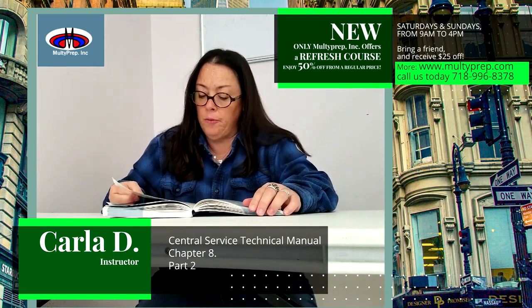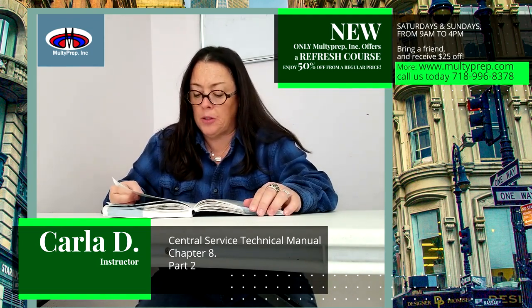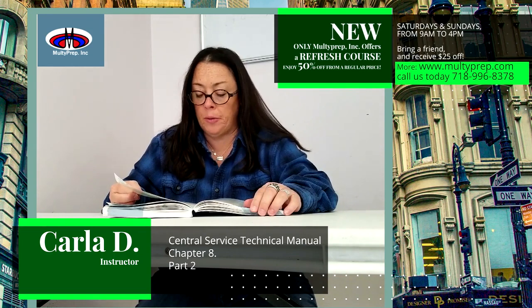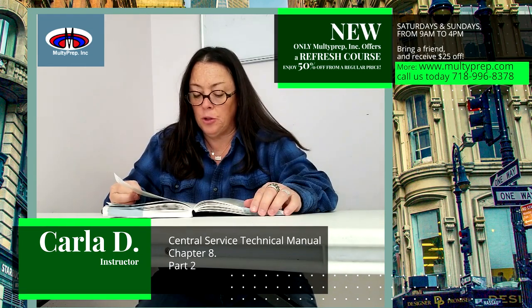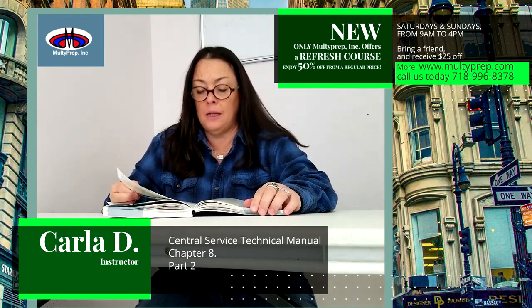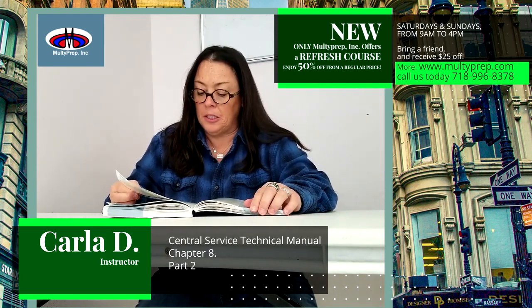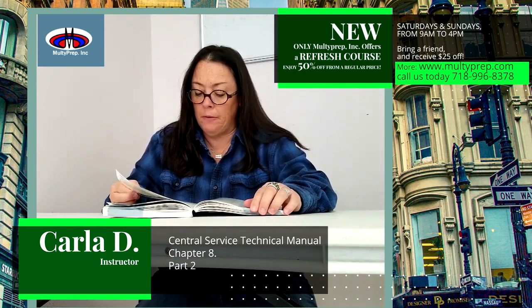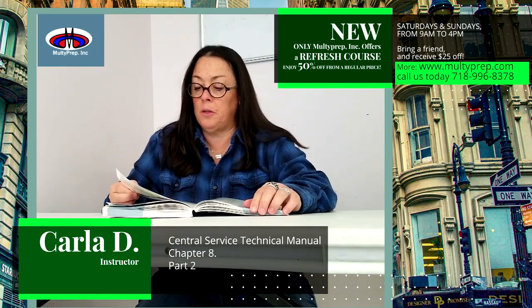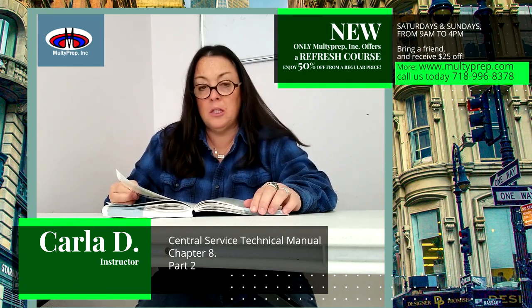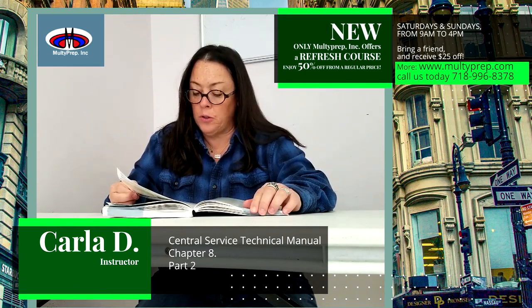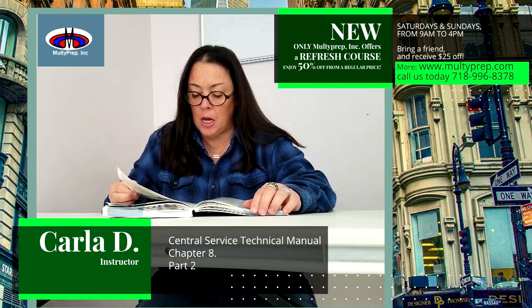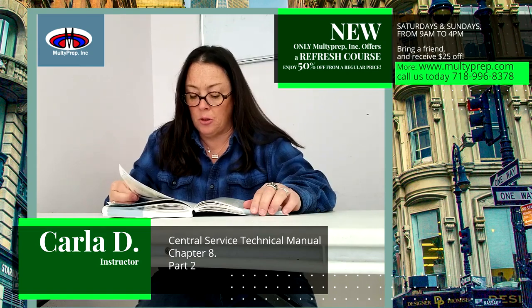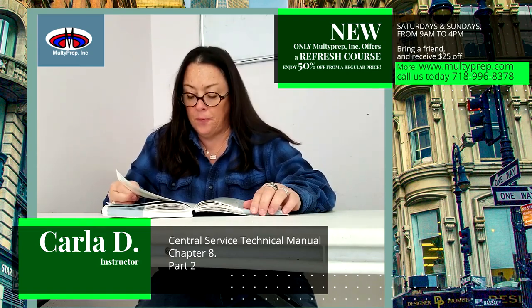Stain and rust removers are used when the normal cleaning process does not remove stains on the instruments. Stains and rust usually result from improper care, such as soaking the instruments in saline. Stain and rust remover can be used after instrument cleaning to restore the luster to stainless steel instruments. These chemicals remove hard water deposits, rust, scale, and discoloration from instruments and processing equipment.